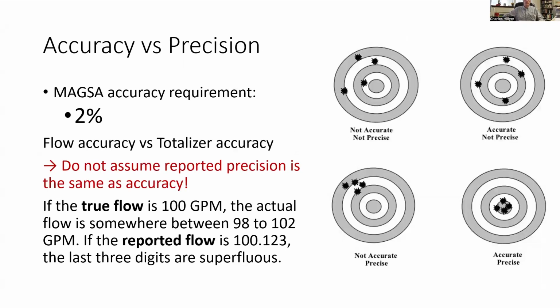Now, one of the really important things about a flow meter is that it be accurate. If you're getting data out of this flow meter and it's not accurate, it's not data, it's noise. MAGSA has a very specific accuracy requirement: the meter must be accurate to within 2% of the reported flow. It's important to understand that that's the instantaneous flow rate accuracy. All the meters that are available to you as part of the MAGSA program comply with this 2% accuracy requirement.